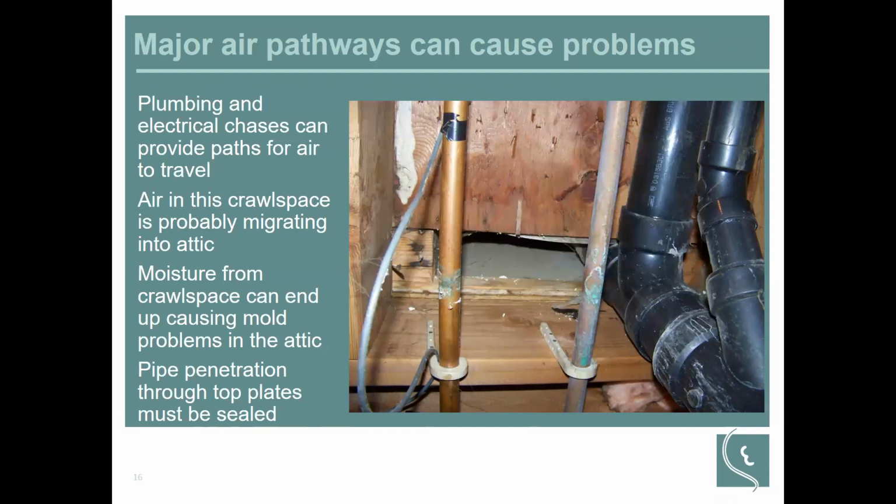And building officials these days are fairly good at requiring builders to caulk around penetrations, electrical penetrations, plumbing penetrations, and things of that nature. And you can imagine here also where the warm, moist air could condense on the backside of these walls if somebody had the air conditioning turned down pretty low. So that would create a very high humidity environment in that chase and cause all kinds of problems. And these problems aren't immediate. They sometimes take years to appear before somebody notices that we have a serious problem here.